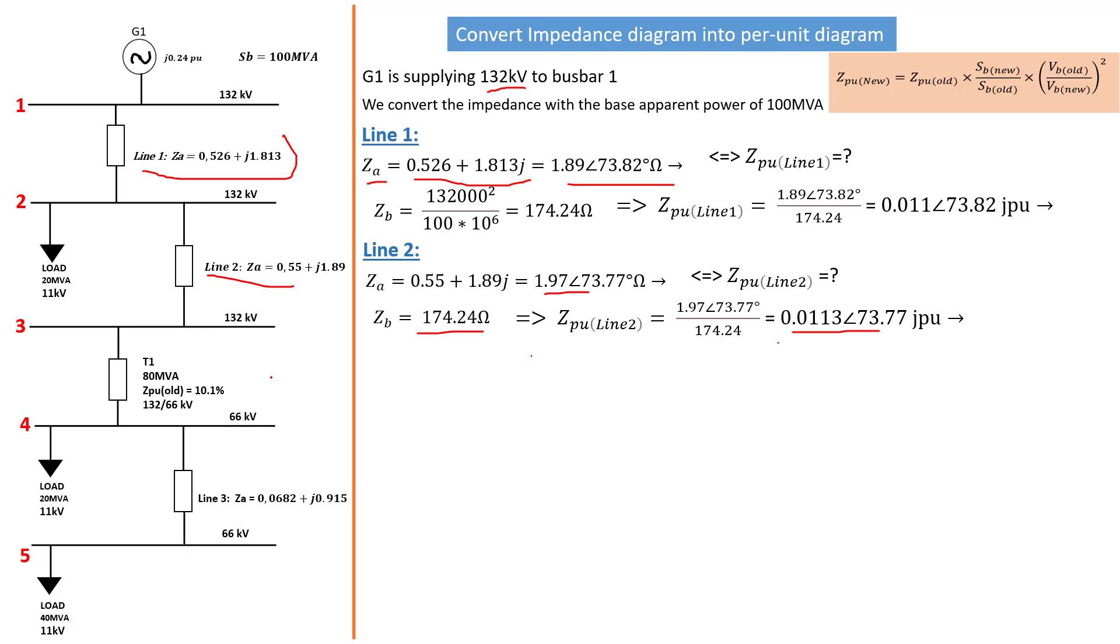Moving on to the transformer T1. The transformer T1 is a bit complicated but we've done it before. It's a step down transformer. The transformer has a rated apparent power of 80 MVA, which is going to be considered as our SB old. The Z per unit old is 10.1, that is 0.101 per unit.